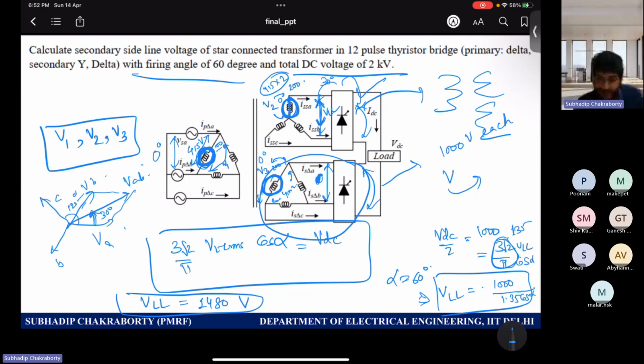So that's why a 30 degree line phase shift came, not due to the transformer in this case, because transformer phase to phase doesn't give any phase shift. It is only the line voltage arrangement that introduces the phase shift. Is this point clear or not?